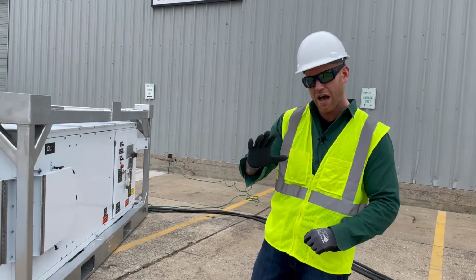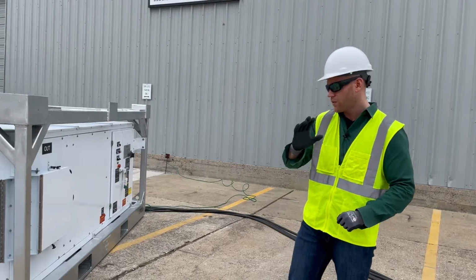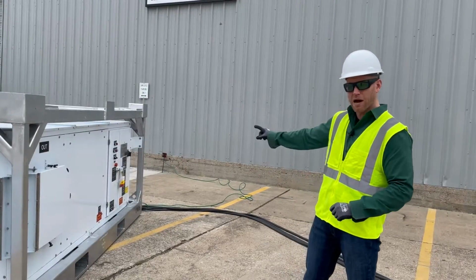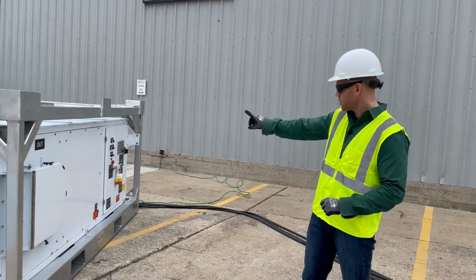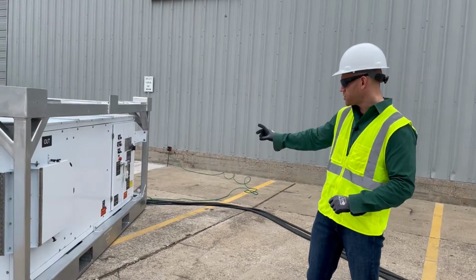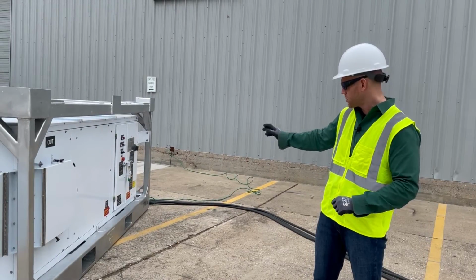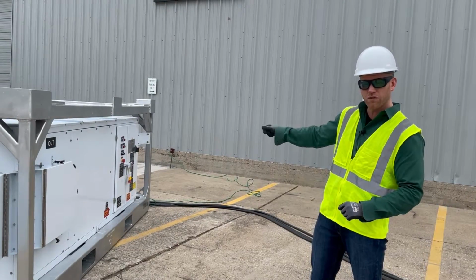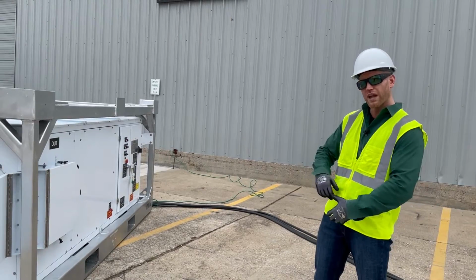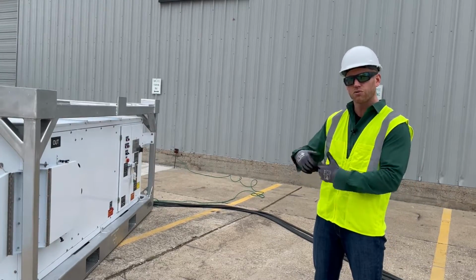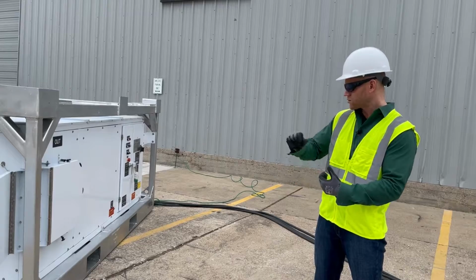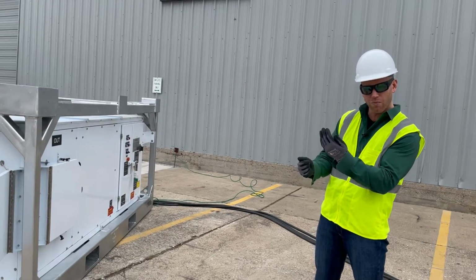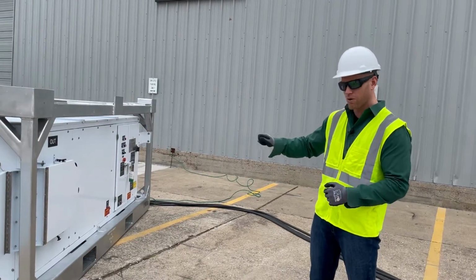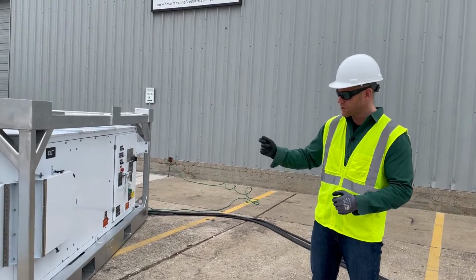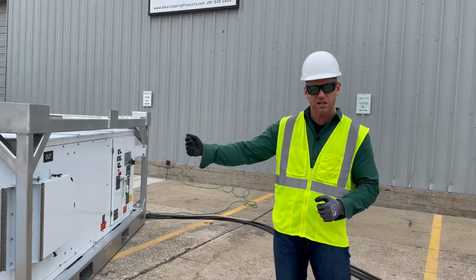And step number 5, go through the startup steps we went through. Apply the correct power to the unit. Start the unit with the control power switch in the off position and the airflow switch in the off position. Turn the unit circuit breaker from off to on. Wait for our phase monitor to go through its time delay sequence. Turn control power on. If we get a control power light on, then go ahead and turn the blower or airflow switch in the on position, and then crank up the blower as needed once we start up.